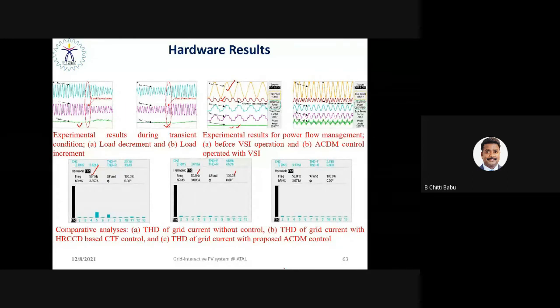And the THD has been reduced from 20.1% to 4.64%. This is with the controller; without the controller, the fifth order and seventh order harmonics are dominating, but with the controller that has been reduced to 4.64% with negligible lower order harmonic components. And with multifunctional inverter operation, or ACDM, active current detection method of control, it is further reduced to 2.91%. So with negligible lower order harmonic components, it injects only the fundamental current component of 50 Hz.